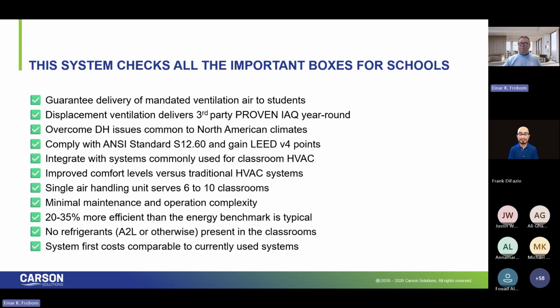It's air, it's water. It's less maintenance because we don't have any moving pieces and parts. We don't have any refrigerant in the occupied spaces. We don't have to deal with that in the design, or worse, if something bad happens in operation. And 20 to 35% more is so conservative. I showed you the two identical buildings. That's a 40% savings, and for system costs that are very comparable to other well-designed systems.